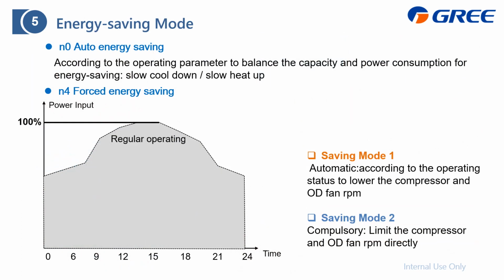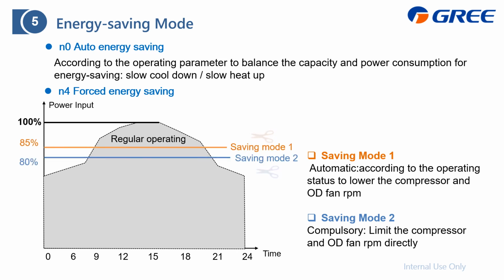Energy saving mode. That means the system will check the operating current to lower the system output, which is to save power. And we offer you two levels, level 1 and level 2. Level 1 can save up to 15%, and level 2 20%. And to activate it, you can set it from the outdoor unit PCB by selecting function code N4, or from the wire controller of any indoor unit, or from the remote monitoring software on the PC.